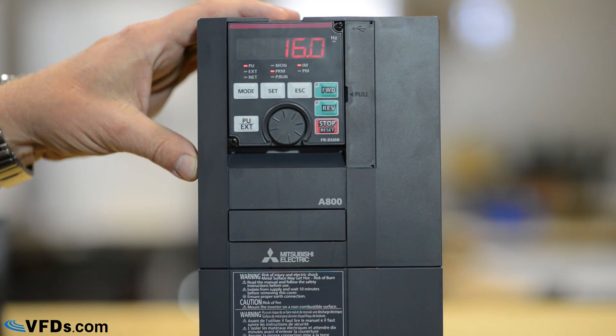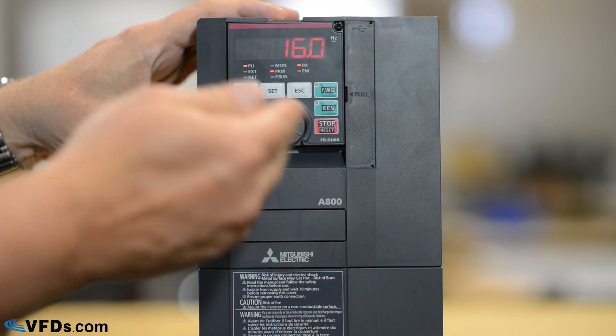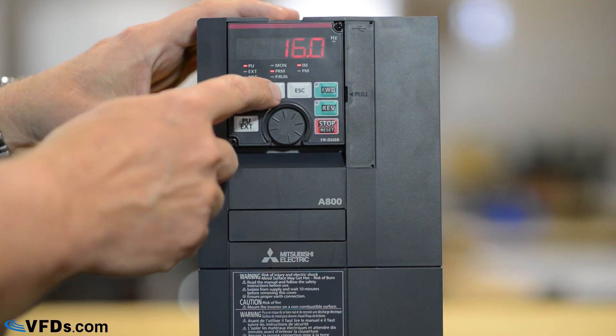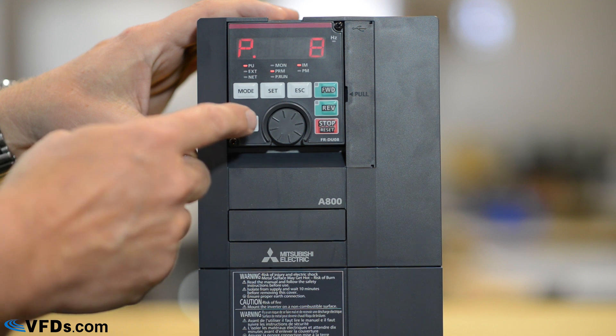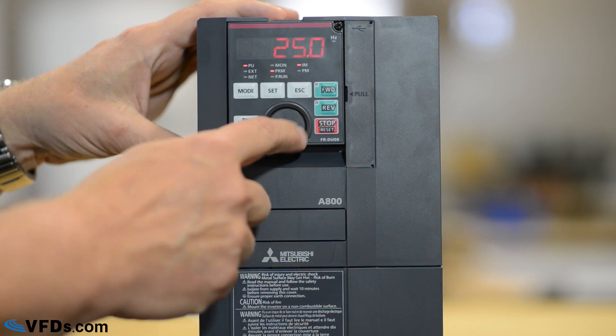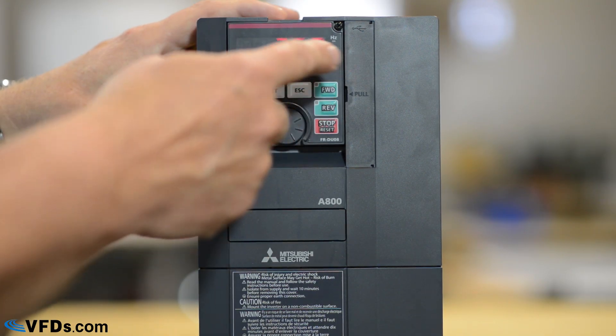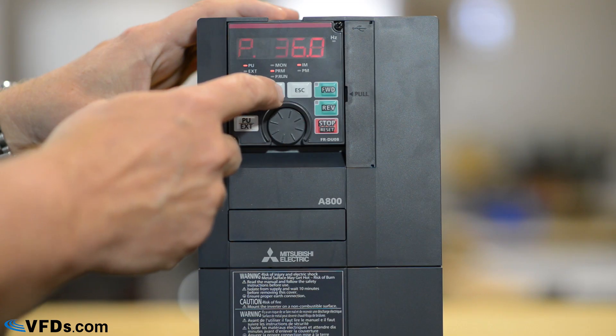I press set and our acceleration time is now 16 seconds — it will go from zero to full speed in 16 seconds. I push set again and it goes to parameter 8. Parameter 8 is my deceleration time. That's set for 25 seconds. Let's move that out to 36 seconds. Press set again and it takes that number.